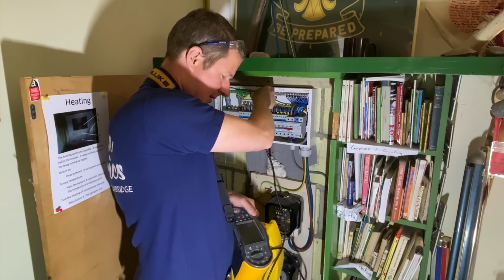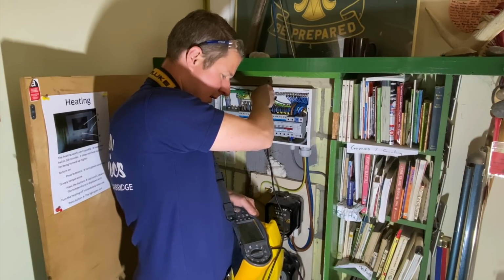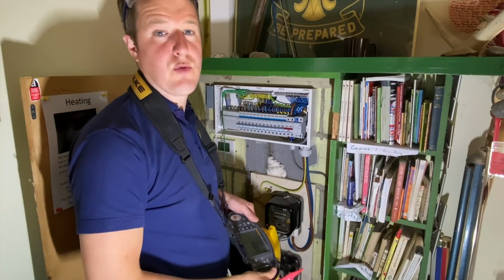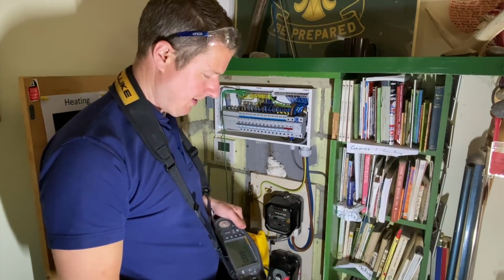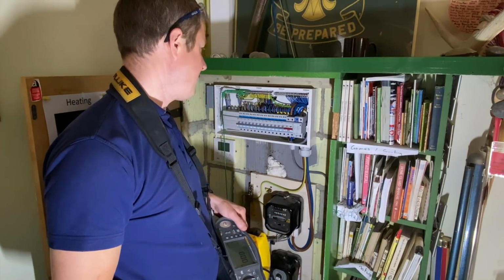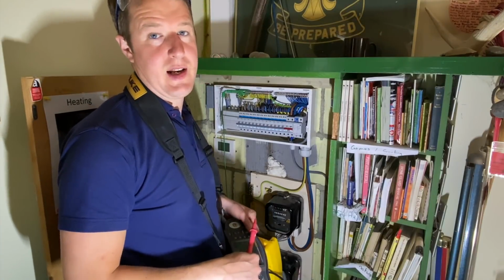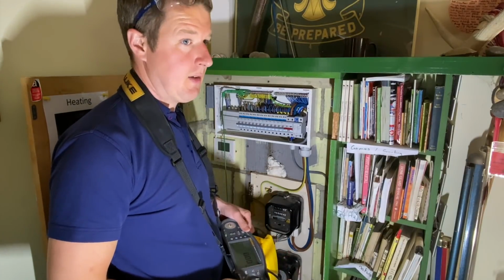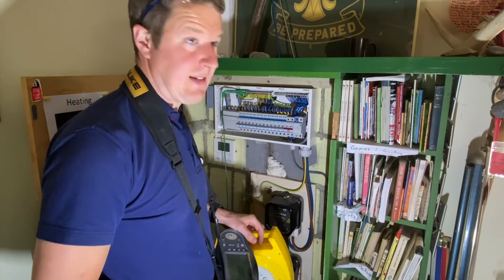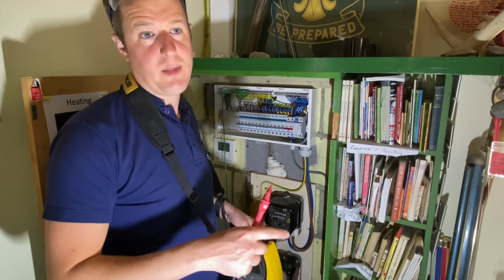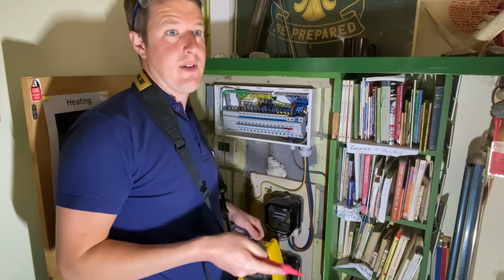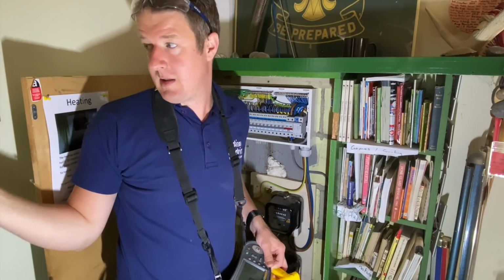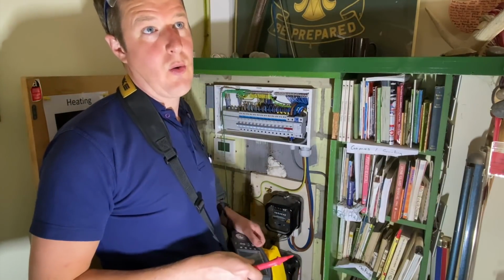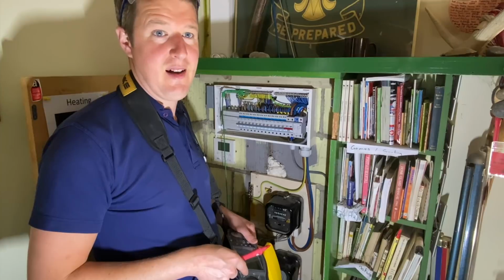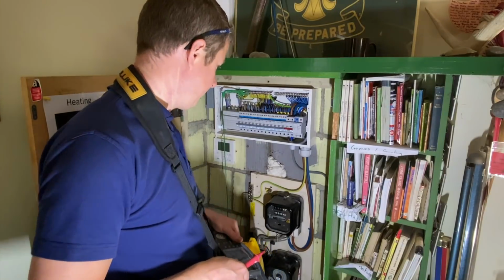The resistance of the leads is 0.96 ohms. So now when we test, the tester has removed that resistance of the leads from the test reading, so it's giving us an accurate reading of just what the circuit resistance is. And so literally I'm going to just wander around the property now, testing out all the light fittings, the sockets, the switches, etc., to make sure that all the exposed metalwork that needs to be earthed is earthed.